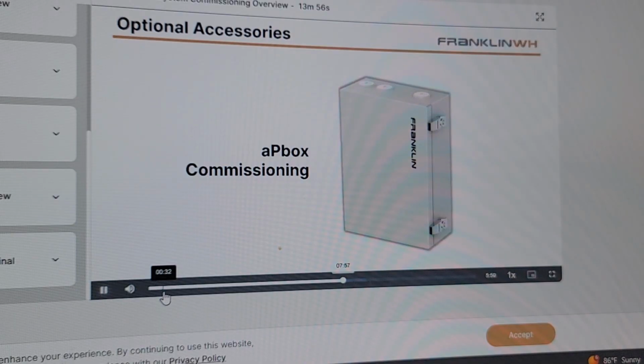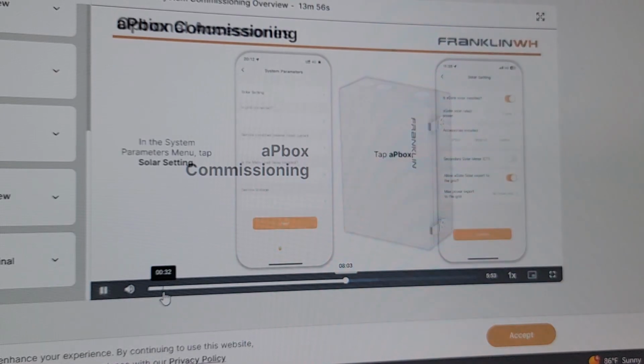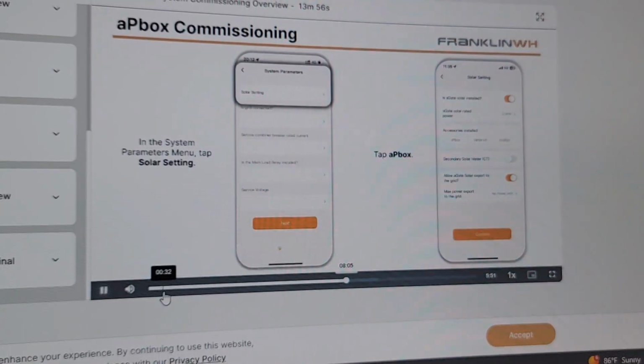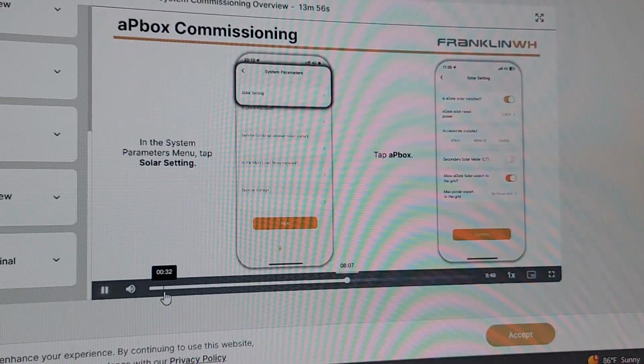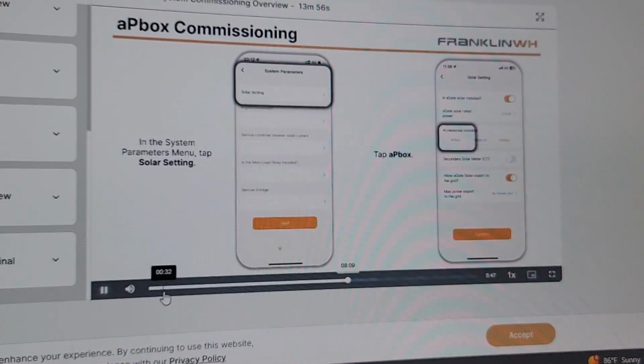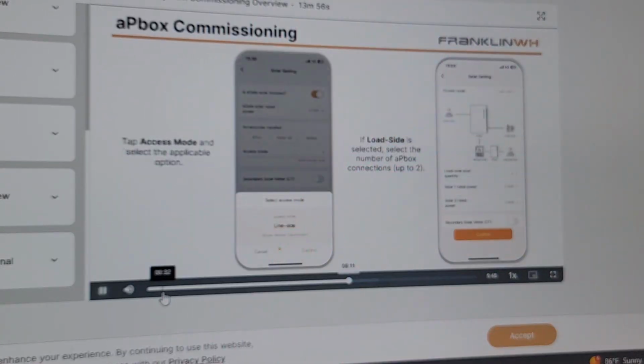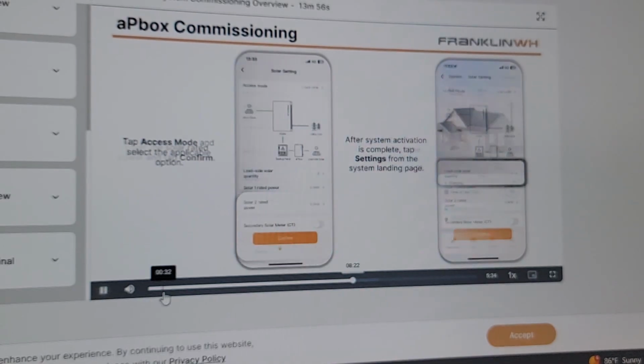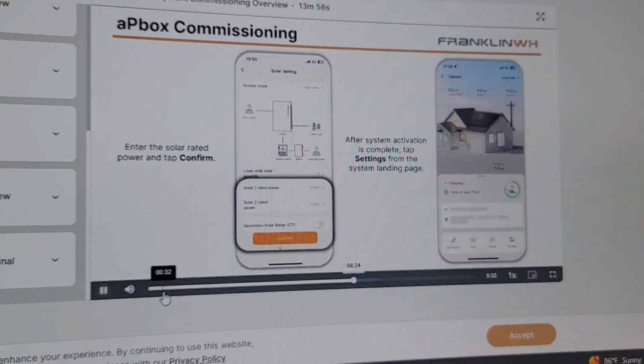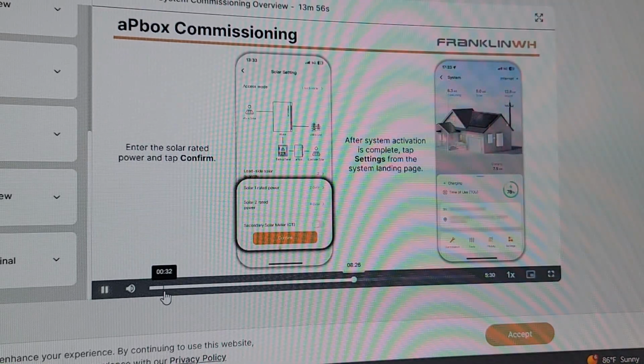The following information will detail the commissioning of the optional FranklinWH AP box. In the System Parameters menu, tap Solar Setting. Then, tap AP box. Tap Access Mode and select the applicable option. If Load-Side is selected, select the number of AP box connections. Next, enter the solar rated power and tap Confirm.